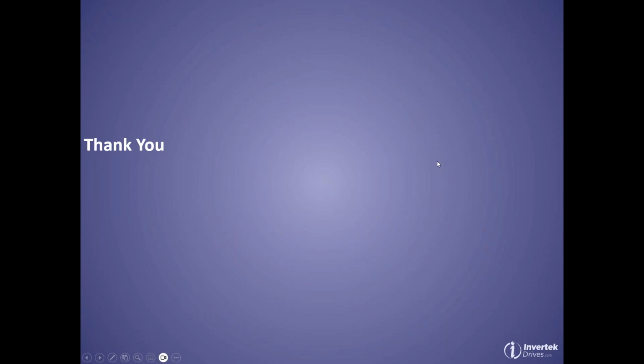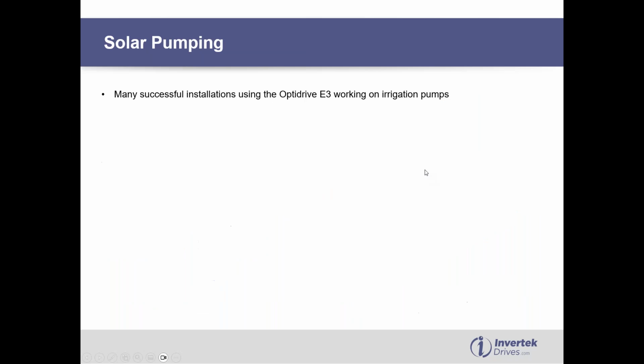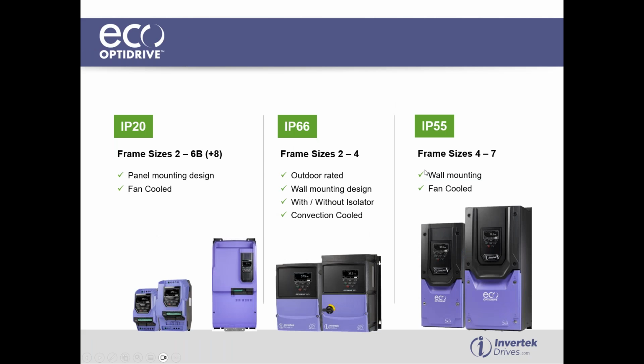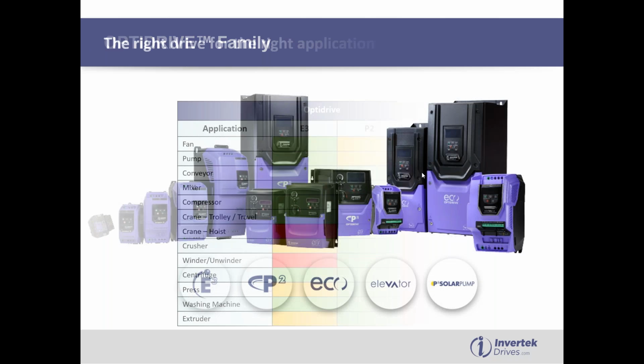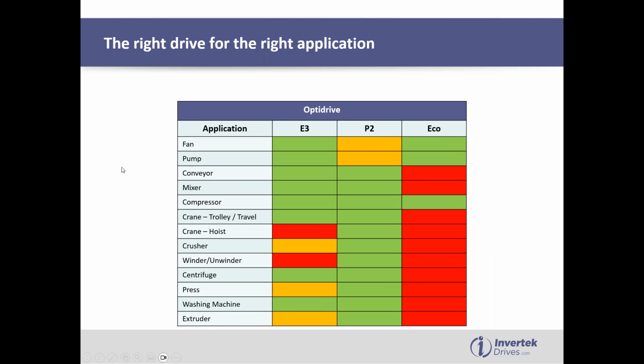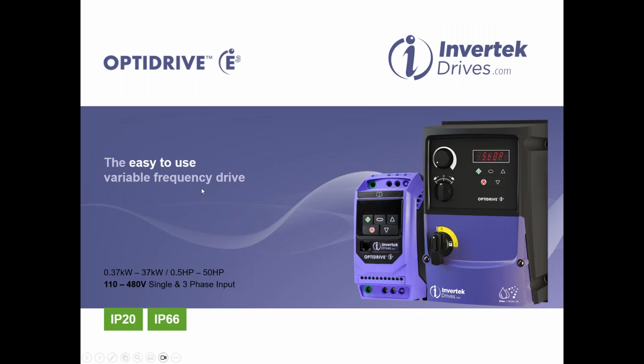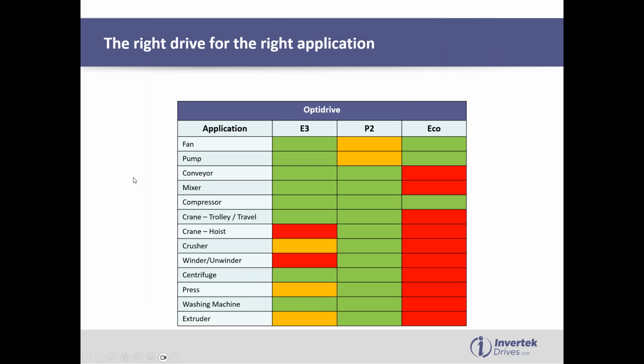Oh, okay, yeah, this is a quick way of showing that. If they have a nameplate of a motor and they're going to select a VFD. Oh, sorry, I see what you mean. The important thing they need to know is the motor rated current. You should always select the drive for the motor rated current.